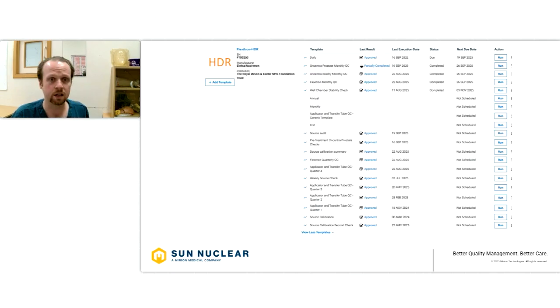Taking a look, this is our current status of templates for HDR, so including daily run-up, pre-treatment checks before prostate procedures, a procedure for days where we don't want to run up the machine, there's no treatment. Your monthly QC for the Flexitron itself, for our gynae and prostate TPSs, as well as procedures for our source calibration and our annual applicator QCs.